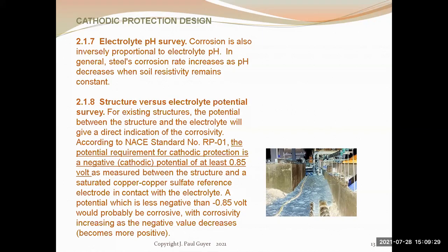But you can only measure this structure to electrolyte potential if the structure exists out there on the ground. Now, a little further on, there's a figure that will make this structure to electrolyte piece of field work a little clearer. But again, the structure to electrolyte potential can only be undertaken as field work if the structure exists out there in the ground.